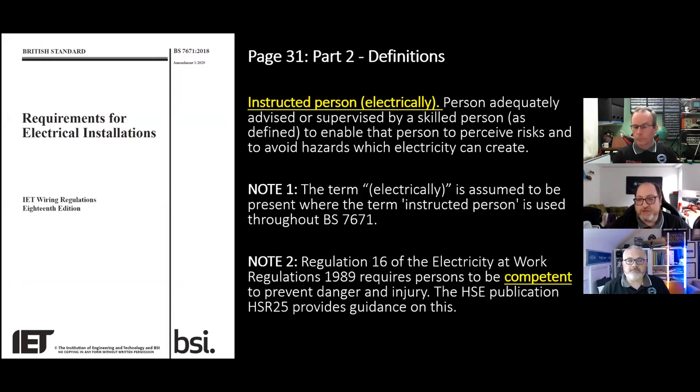And this is something I do a lot of training in, trying to develop roles, responsibilities training and duty holder training for companies who run businesses, who run engineers, to understand how the law works in this area. And authorizations, roles, responsibilities: if you employ the services of an engineer, they may have some level of competency, but they may want to authorize them in certain areas. Some of you guys may have gone to certain factories, certain clients, where they'll authorize you to receive permits to carry out isolation, but they may not authorize you to do live work. They may not authorize you to access their switch rooms. There are many different levels of authorization.